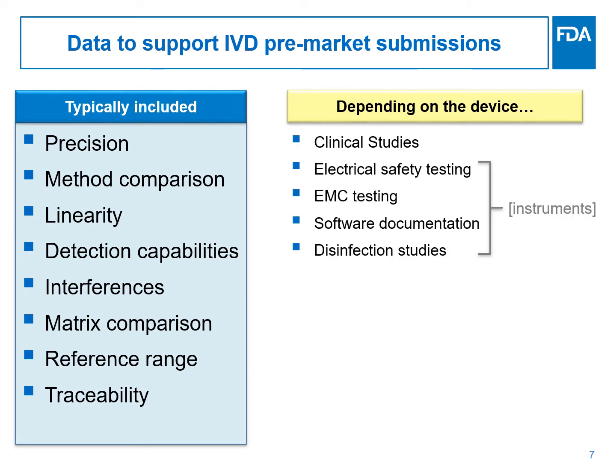Depending on the device, some IVDs will require additional studies. For example, the link between the analytical performance and the clinical performance might not be well defined. In these circumstances, clinical information may be warranted. Other studies depend on the composition of the test system. For example, if the new reagent is used with a new instrument that FDA has not cleared before, then electrical safety, software documentation, and electromagnetic compatibility testing should also be included.